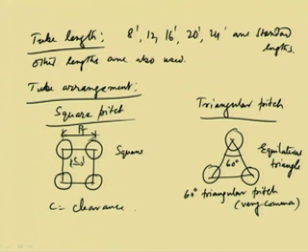Okay. Similarly, here the center to center distance is called PT, the triangular pitch, the pitch of the triangle. So the center to center distance between two tubes is called the pitch, whether it is a square pitch or the triangular pitch, in both cases. In square pitch these angles are 90 degree, and it makes a square, and in this case it makes a triangle, usually an equilateral triangle, that means they are at 60 degree angles.